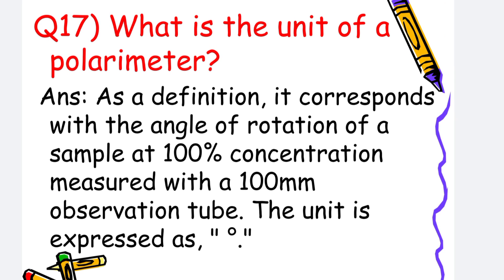What is the unit of a polarimeter? By definition, it corresponds to the angle of rotation of a sample at 100% concentration measured with a 100 mm observation tube. The unit is expressed as degrees.